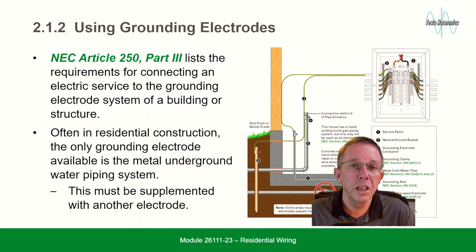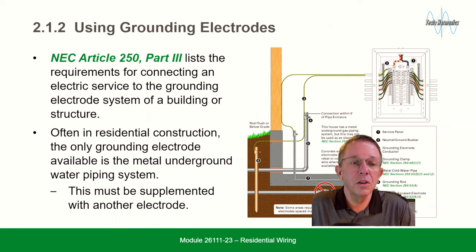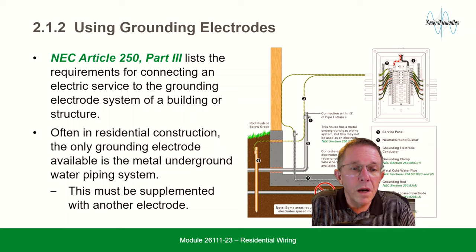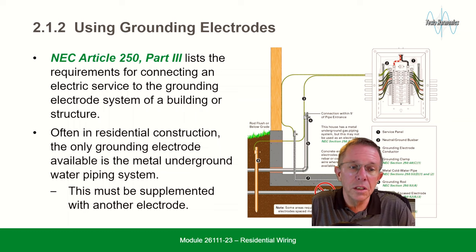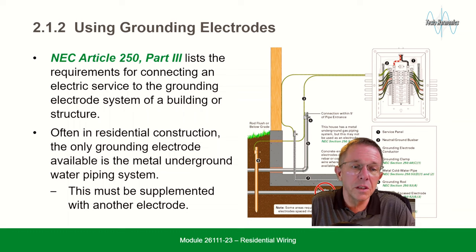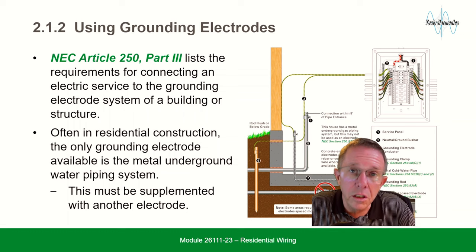Using grounding electrodes: NEC article 250, part 3, lists the requirements for connecting electric services to the grounding electrode system of a building or structure. Often in residential construction, the only grounding electrode available is the metal underground water piping system. This must be supplemented with another electrode.